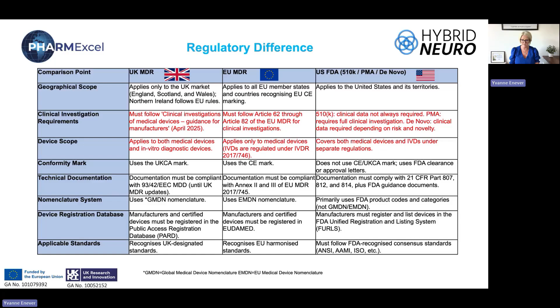So you can see the subtle differences, but it's really important to think about what that means for you. Some of our clients who want to work, say, in the UK and in Europe, we would probably encourage them to comply with the European MDR, because meeting those standards, you're inadvertently going to meet the standards of the UK MDR at this stage, where we're sitting in terms of our regulations. So it's really thinking about how much work you're going to need to do both in your preclinical and into your clinical spaces to move your device through the conformity assessment route.